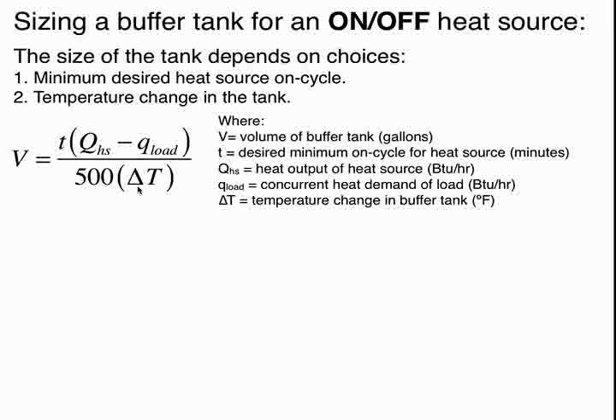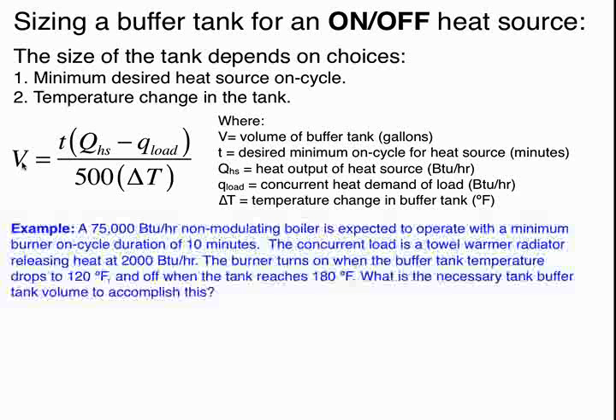And if you're trying to decide that, again, there is no standard on this. I would suggest something from 40 degrees Fahrenheit on up. Basically, the wider the delta T, you can see it in the math here, the larger this gets, the smaller V, the volume of the buffer tank, gets. So let's do an example.